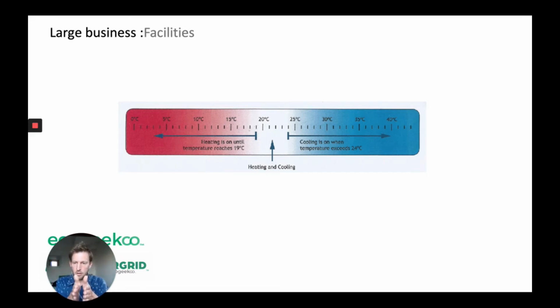So it's a pretty tight deadband between heating and cooling. During this time of low occupancy or no occupancy, if you want to make sure there's some base heating to keep the buildings dry if it's very, very cold, you can basically widen the deadband to say don't activate the heating unless it gets below 12 degrees in this space. And likewise with the cooling, you can push that pretty high, unless you have, say, a server room that you're worried about, but most of those will have their own dedicated air conditioning unit. So pretty much you can make a huge impact just by changing the set point and widening that deadband.